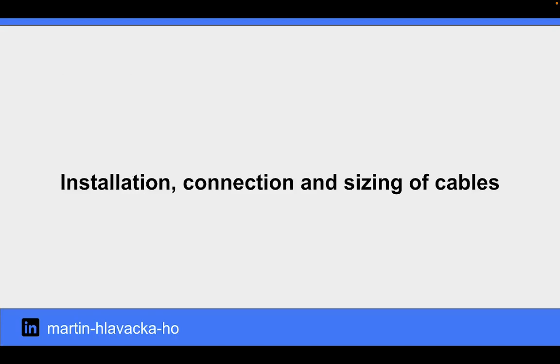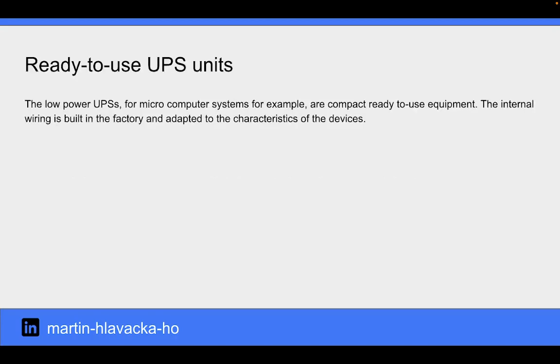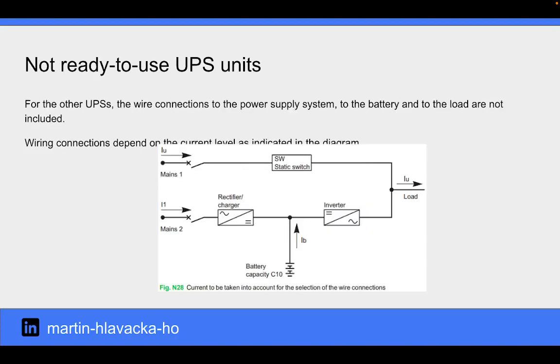Installation, connection, and sizing of cables. The low power UPSs for microcomputer systems, for example, are compact, ready to use equipment. The internal wiring is built in the factory and adapted to the characteristics of the devices. For the other UPSs, the wire connections to the power supply system, to the battery, and to the load are not included. Wiring connections depend on the current level as indicated in the diagram.